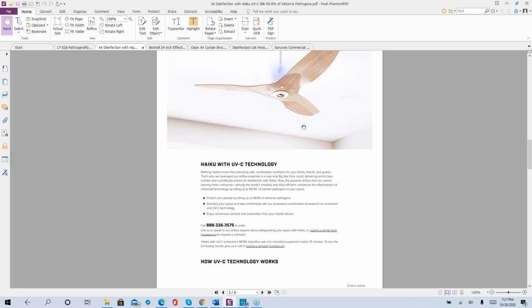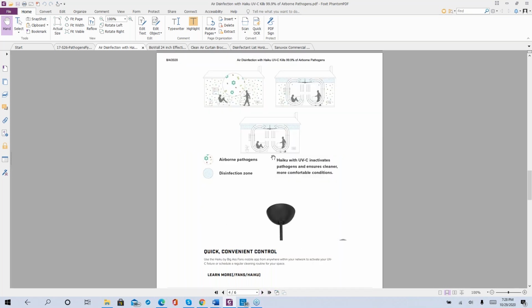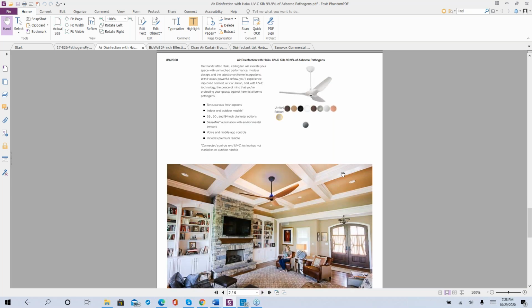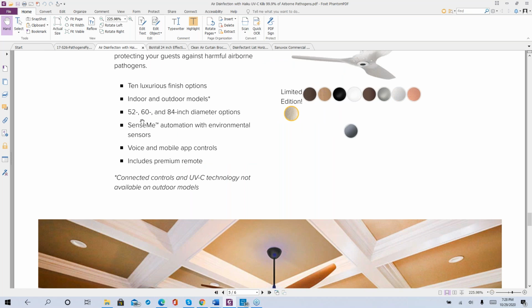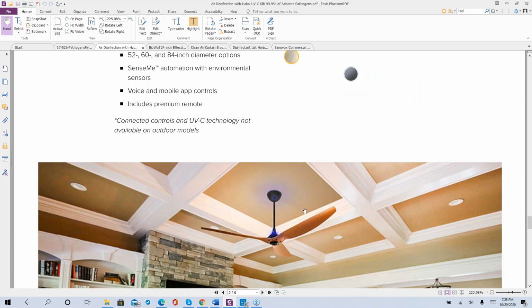But Big Ass Fans came out with this idea that we're going to put a UV light onto a paddle fan. And that paddle fan then gives you this circulation from the occupied area up into the kill area. And they make them all the way up to 52, 60, and 84. Let's blow that up. 52, 60, and 84-inch diameter options.